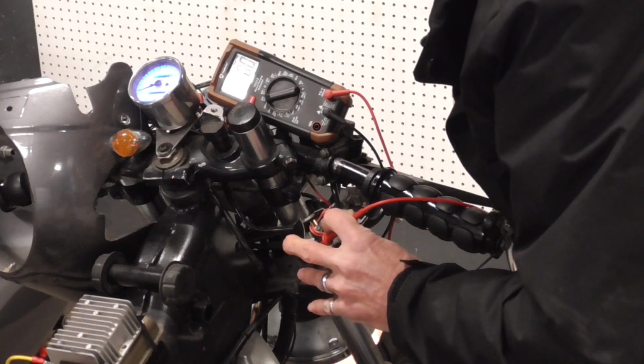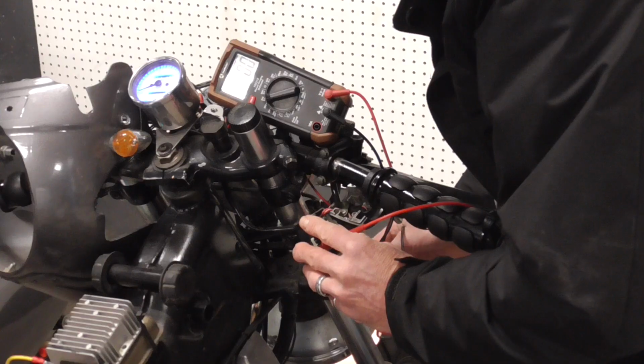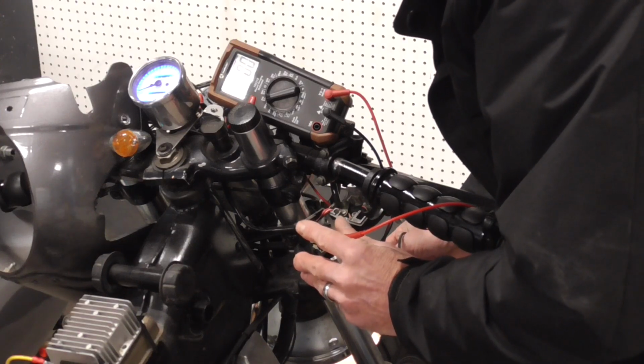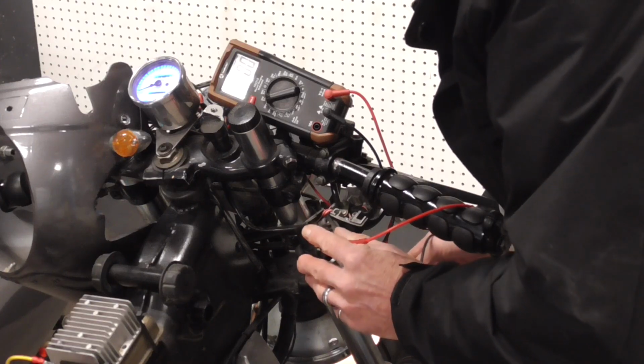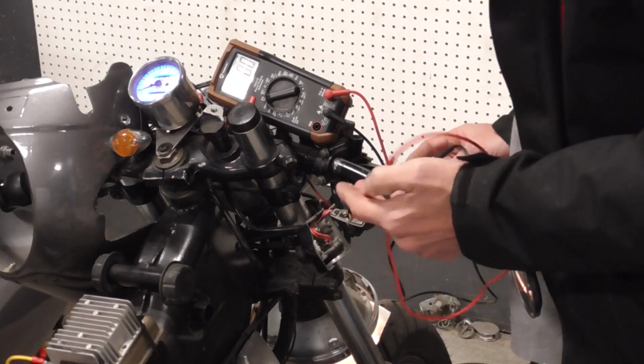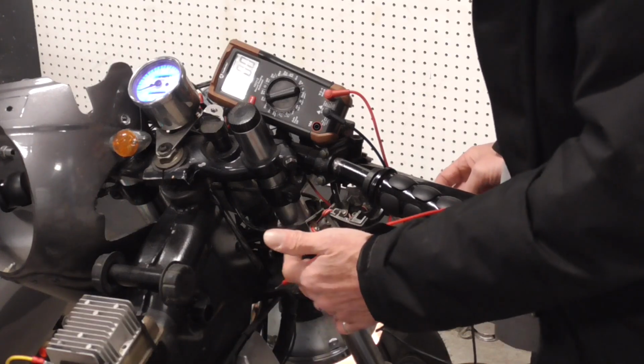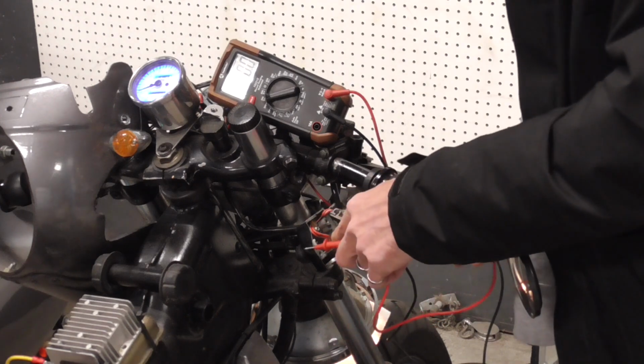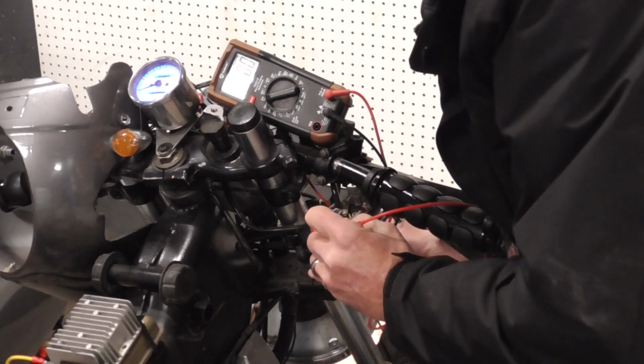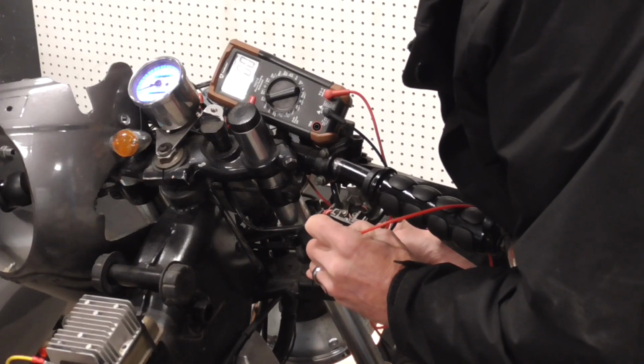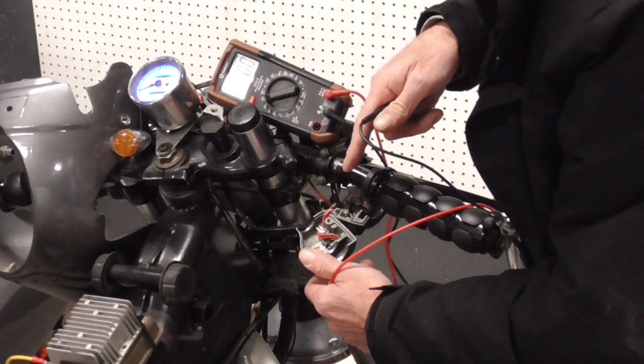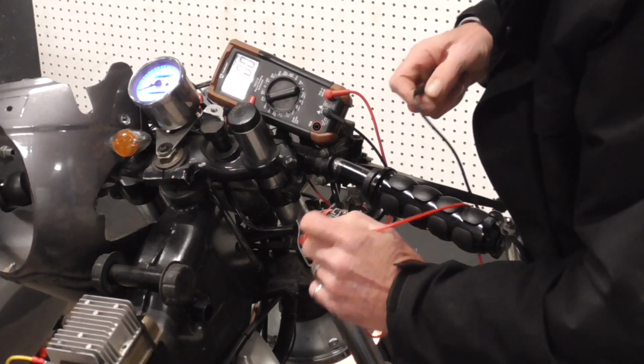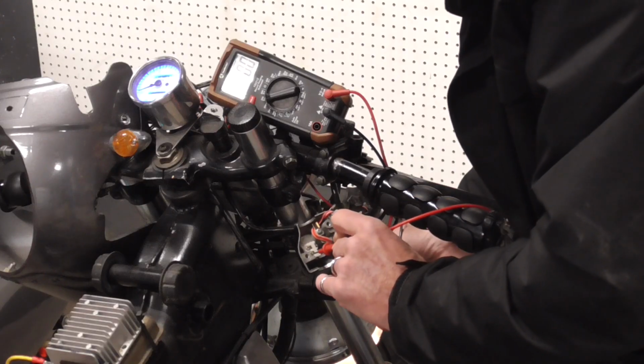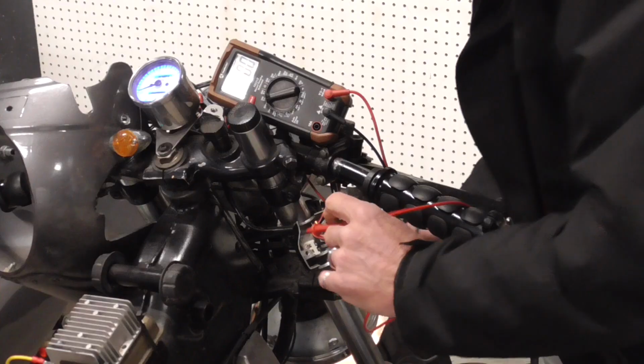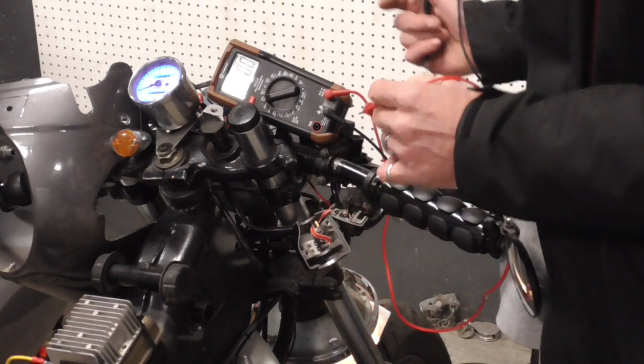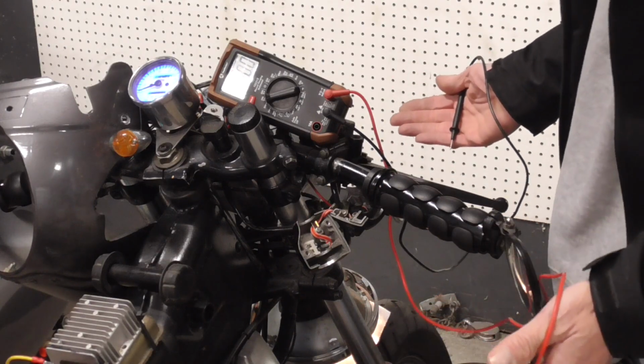And we got nothing, so there's nothing going on here. What does that mean? Well, if we went on down through here there's nothing past this, because this switch carries the red and white wire in and back out. So right here is my problem: something isn't providing power to the switch. If power were coming to the switch and the switch itself were the problem, one of these would still show 12 volts. But I'm not getting any voltage on either of them, so that means somewhere between here and the fuse box is my problem with this red and white wire.